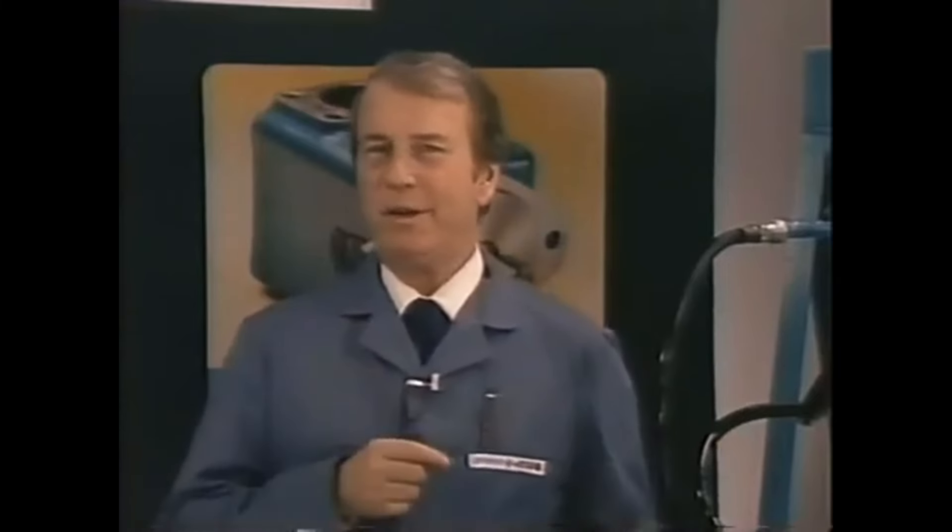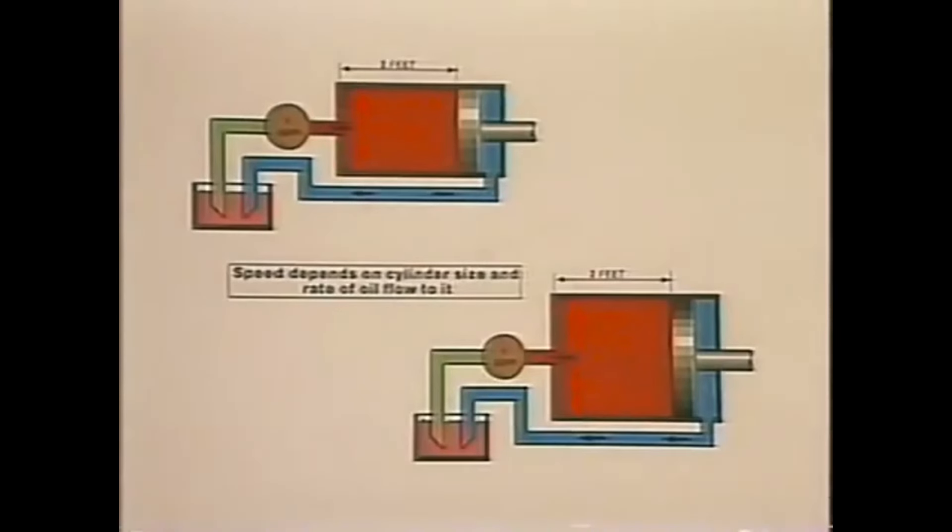I suppose you already know that increasing the relief valve setting doesn't increase the speed of a cylinder or motor. It's the amount of oil available and the size of the actuator that determines speed. That's why little cylinders move faster than big ones in the same system. Increasing the pressure will let you clamp tighter or move a heavier load. But be sure you don't try to exceed what the system is designed to do.